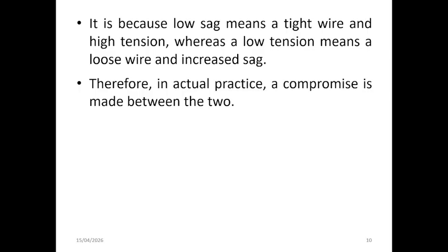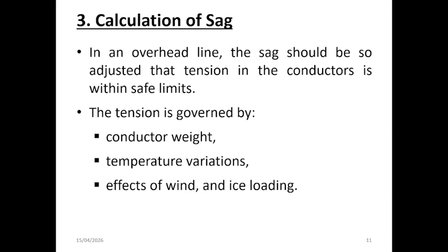Therefore, in practical transmission line design, you always adopt a compromise between sag and tension, selecting values that ensure adequate ground clearance, mechanical safety, and economic efficiency. We will see all of those later on in this following slide. So first of all, calculation of sag.